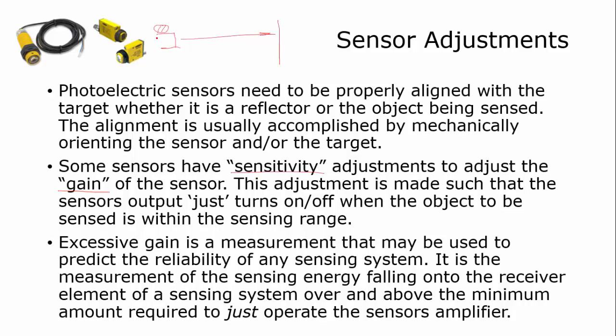Excessive gain is also a measurement that may be used to predict the reliability of a sensing system. It's a measurement of the sensing energy falling onto the receiving element over and above the minimum amount required to just operate the sensor's amplifier. Some sensors will have an adjustment or at least an indicator light to let you know that you have excessive gain.